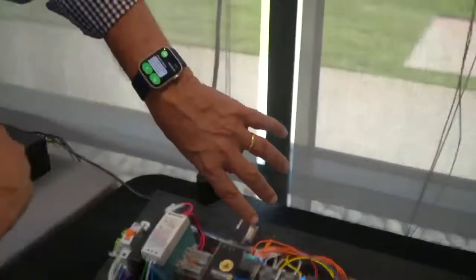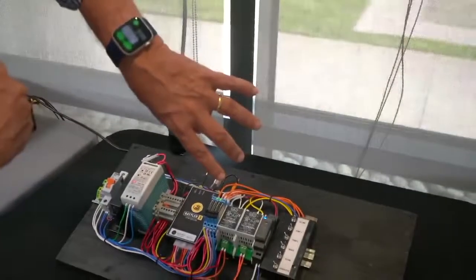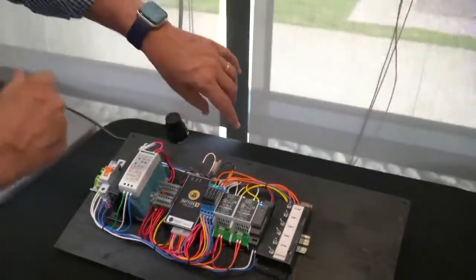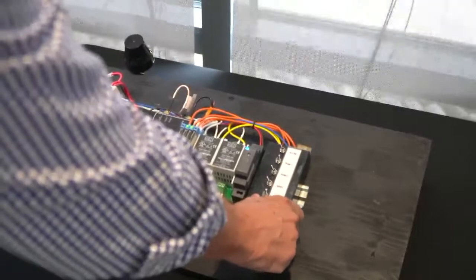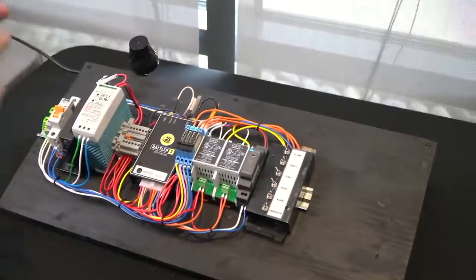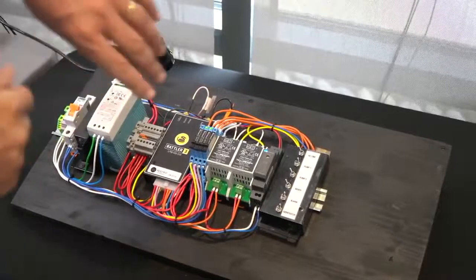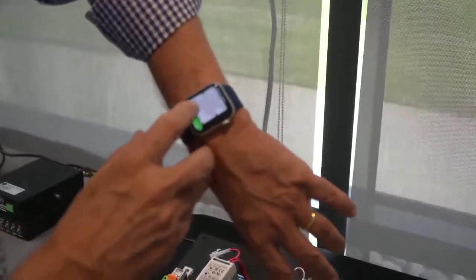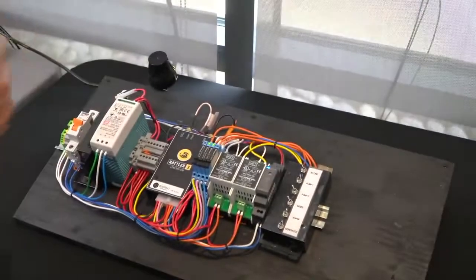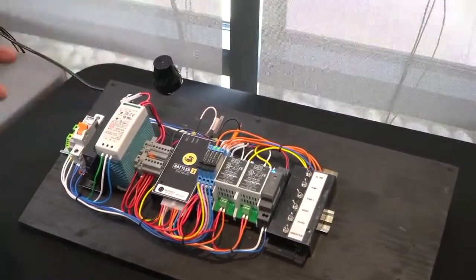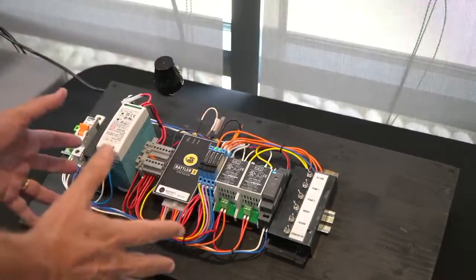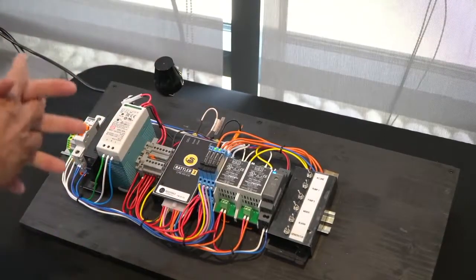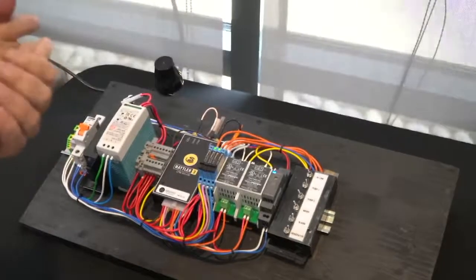Now what you do is you go and check in at Glance, and you see what's happening, and lo and behold, you'll see, oops, it was just a temporary alarm because the AC came back, the substation recovered, the generator turned off by itself. And this is how you do remote monitoring and management of a lift station. And lo and behold, on my watch here, it says lift station type 1 has reported AC restored. That's how effective it is to do remote monitoring and control, with a comparatively simple and inexpensive set of equipment that works cost effectively and efficiently.